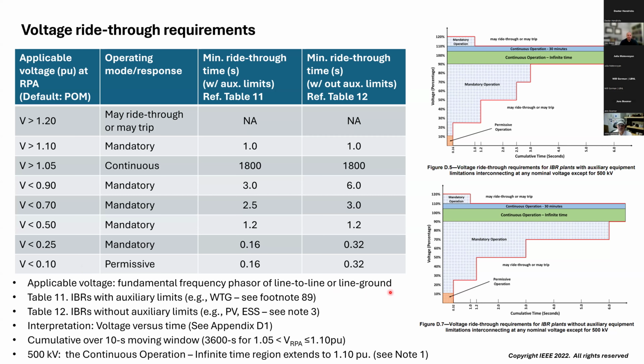When you look at this table or the corresponding pictorial representation from the appendix of the tables, it should be thought of as a voltage versus time interpretation. Appendix D goes into what other potential interpretations there are, a common one being an envelope. If the trajectory lies within, say, an envelope, it has to ride through. But per clause 7, the correct interpretation is to consider this as a voltage threshold versus time requirement.